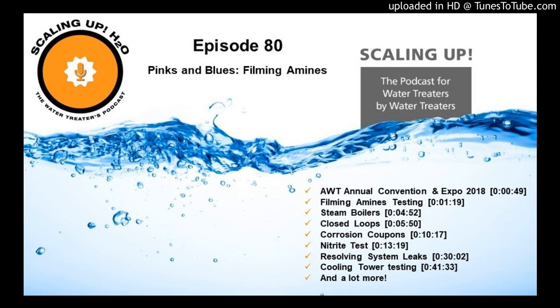So what we then did is we flushed that out, and we had a pretty gnarly looking filter there. Once all that water came out of the system, and of course the water was flowing in a pattern that it wasn't used to flowing, that broke up a lot of stuff. Keeping in mind that the Filming Amine was already working on cleaning up that stuff. So there was a lot of stuff in the system. I think all in all, it probably worked out well, but it would have been great just to see what the Filming Amine could have done without that extra flush. Murphy is always worked into everything that you do, and he was present on this test as well.